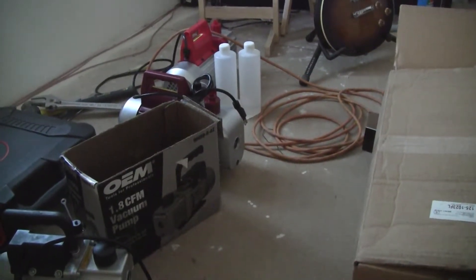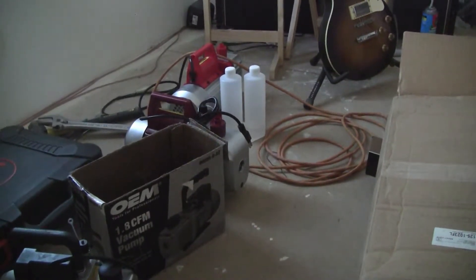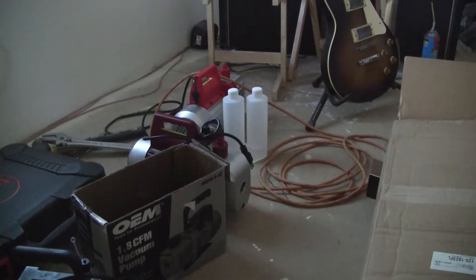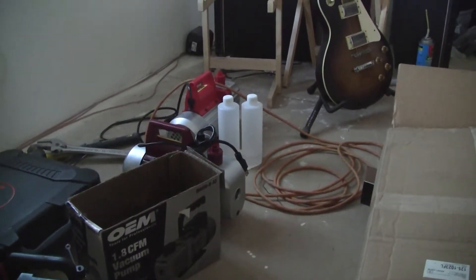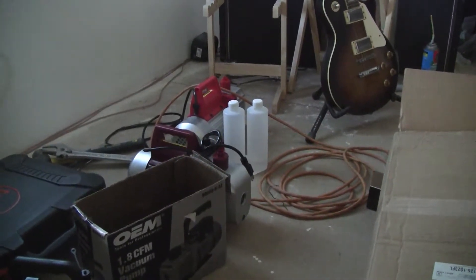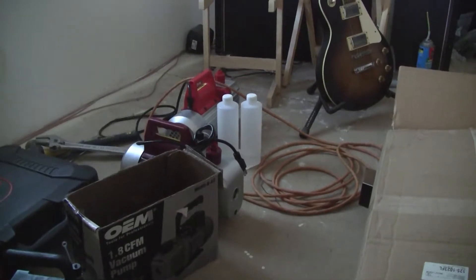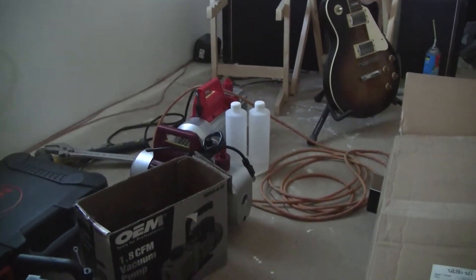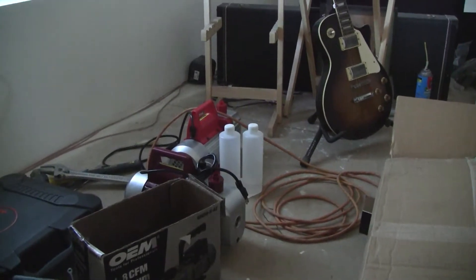We tested three different vacuum pumps and it seems that the higher you are in altitude, the less vacuum you can pull in a relative sense. If you have an absolute vacuum gauge you can get your system down to 29.5 or 100 microns or whatever, but I don't think my gauge has absolute capability, so I'll call the manufacturer and ask them. These two pumps here are perfectly functional from the manufacturer. I was highly disappointed at the time because I didn't know that altitude mattered — I'd never heard that in my life. The last time I was a vacuum tech it was at sea level, so I didn't even have exposure to it.